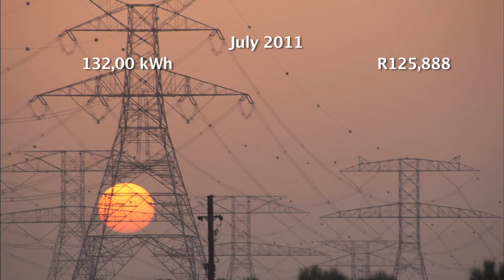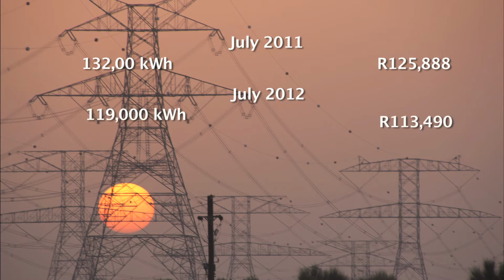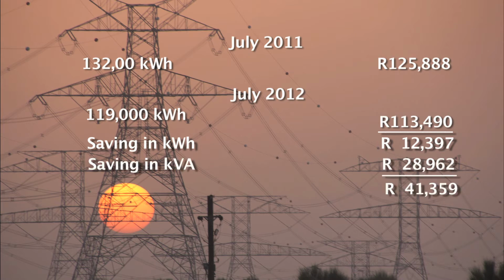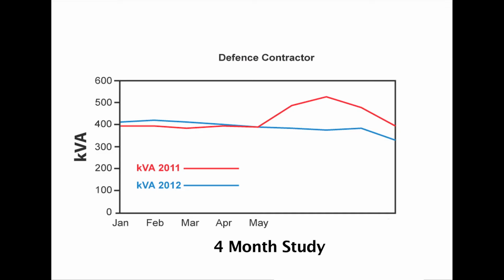So let's see how the amount of power or kilowatt hours used was affected. The 2011 bill indicates a use of 132,000 kilowatt hours for a total of 125,888 Rand in today's terms. In 2012, the usage drops to 119,000 kilowatt hours, which comes to 113,490 Rand, a saving of 12,397 Rand. Now, if we add up the totals, the effective saving for July amounts to 41,359 Rand, or 17.9% of the total bill. The same trend continues when the figures for a period of 4 months are examined.